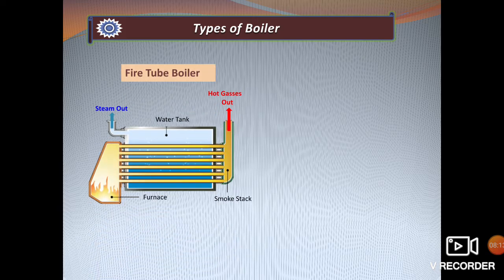There are different types of boilers. The first is the fire tube boiler, which mainly consists of a furnace, a water tank acting as a boiler, and a smokestack. Tubes run through the water tank carrying heat from the furnace, and the smokestack vents heat and gases to keep pressure from rising above the intended level. The fuel is burned inside the furnace, the tubes transfer the furnace heat through the water in the tank, and once heated, the steam is taken out for various applications. Fire tube boilers are the cheapest type due to simple construction, but can be used only for low to medium pressure applications.